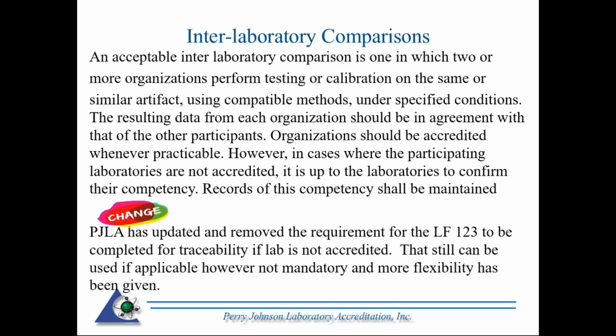All right, an interlab comparison. Bare bones minimum, this is your organization and one other organization comparing the testing or calibrating of the same artifact, and then you compare the data. I say bare bones minimum, and I see it for smaller organizations - it's great if you're able to coordinate with another organization, but if there's only two of them and they're not comparing with each other, your lab might be fine, or it might be on the other side. The other side could be saying the same thing. It's fine if you agree with each other, but if you don't, it's really, is it us or them?